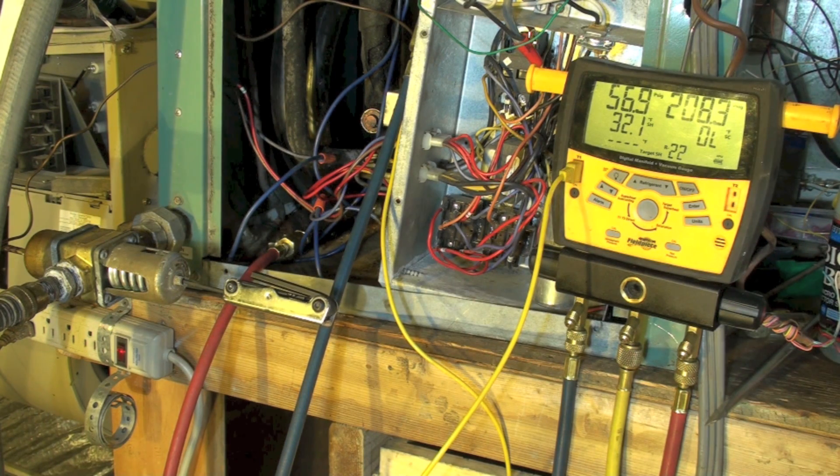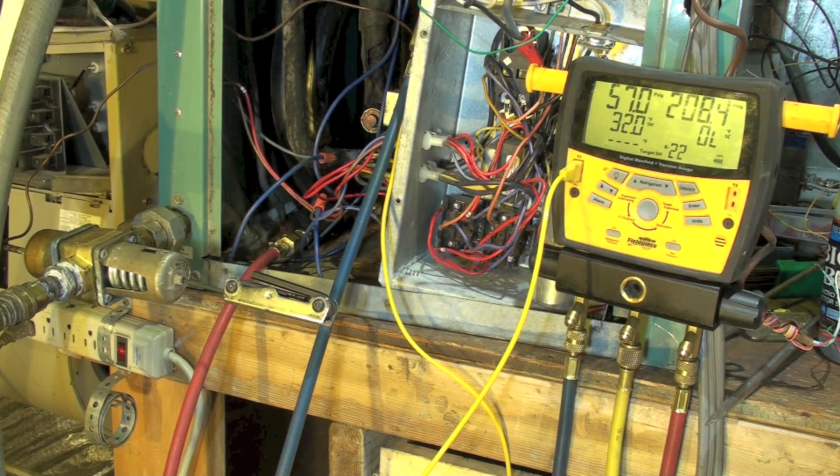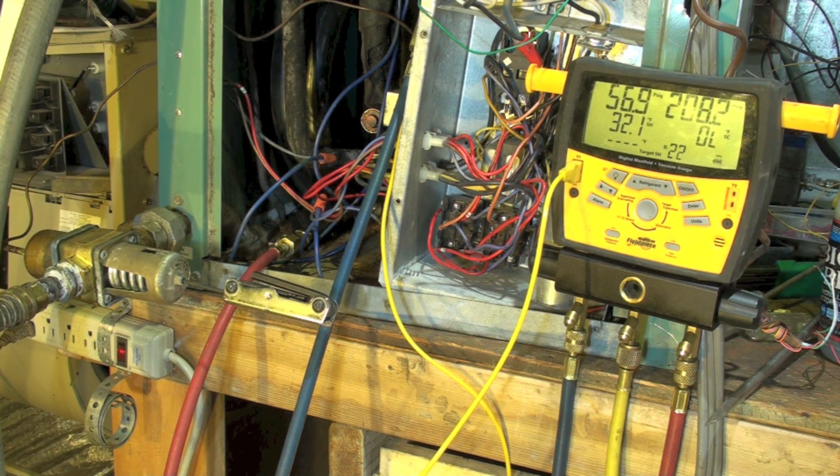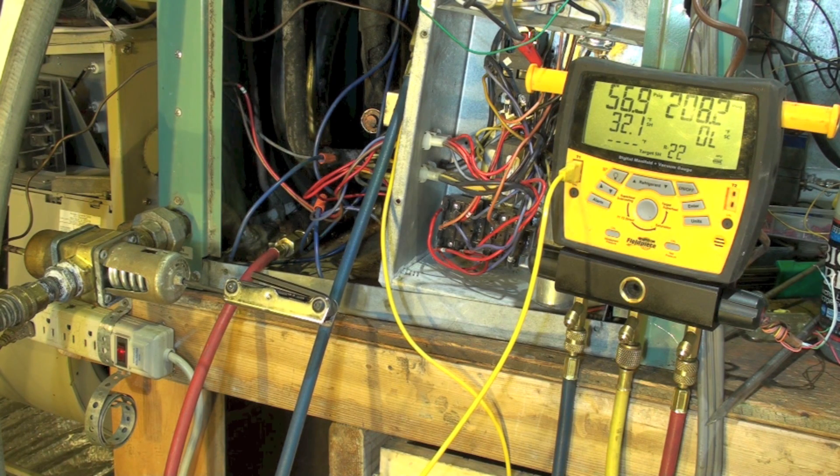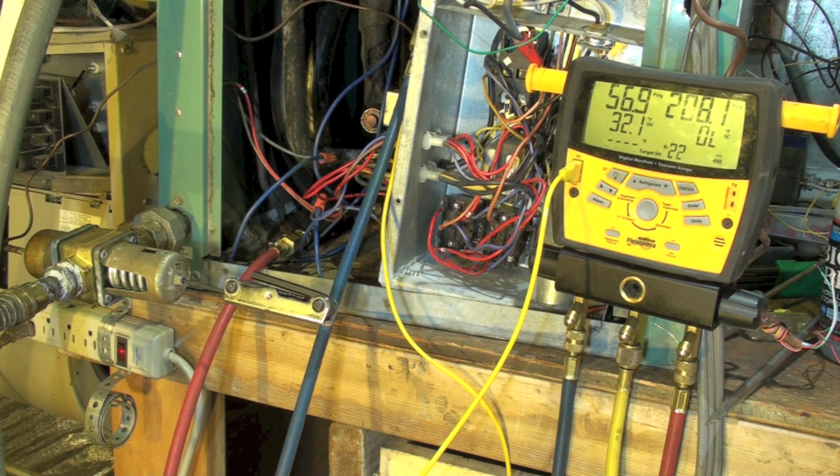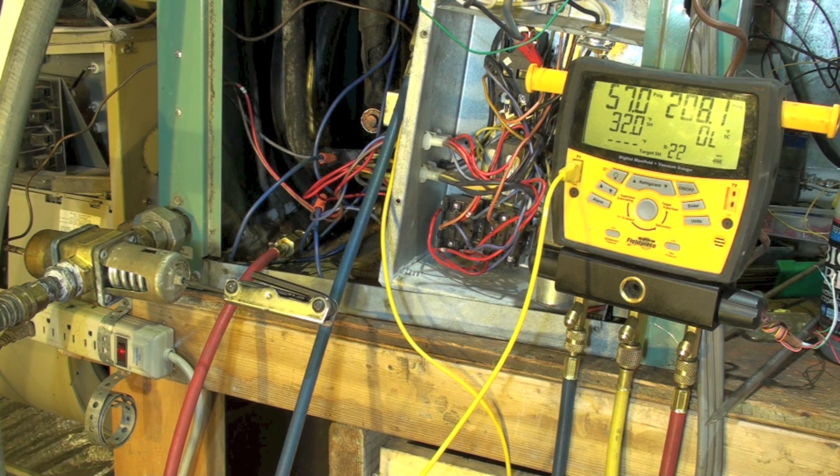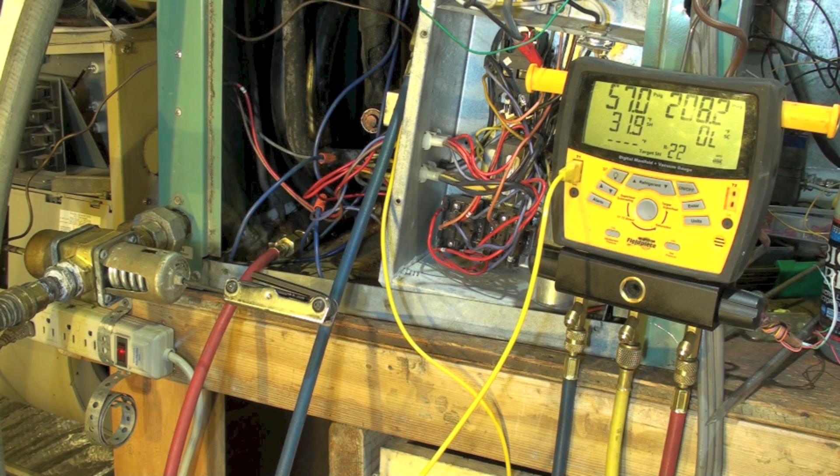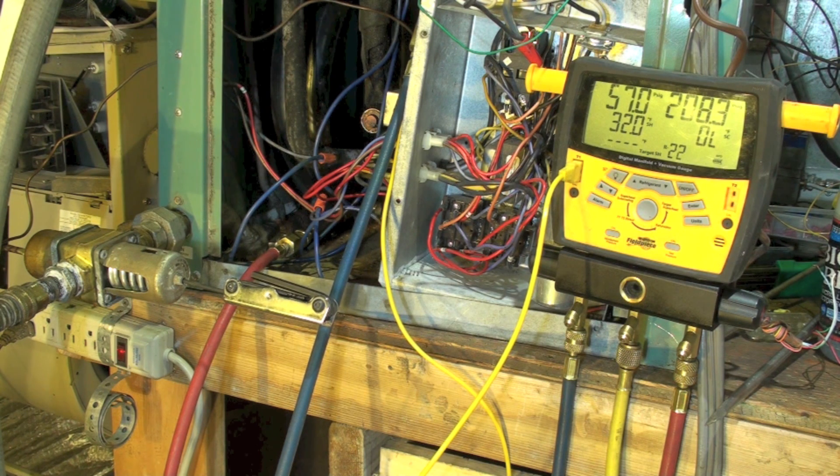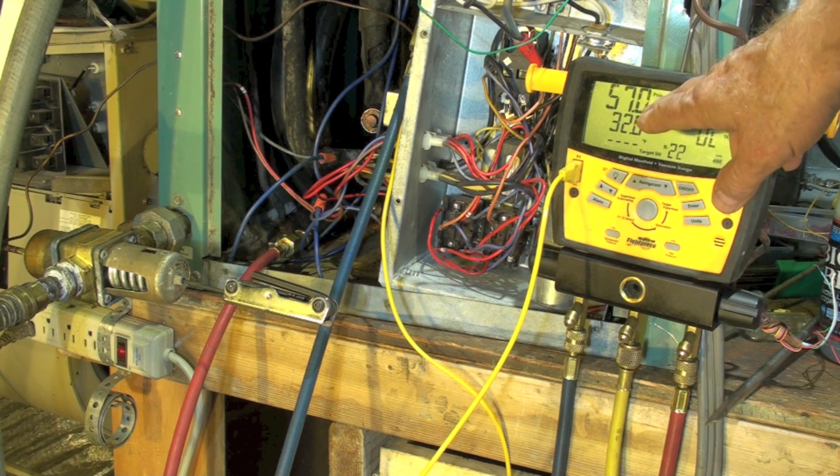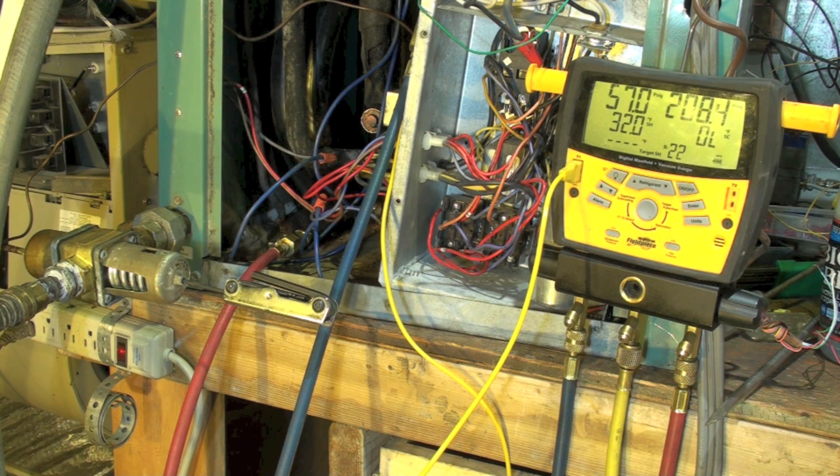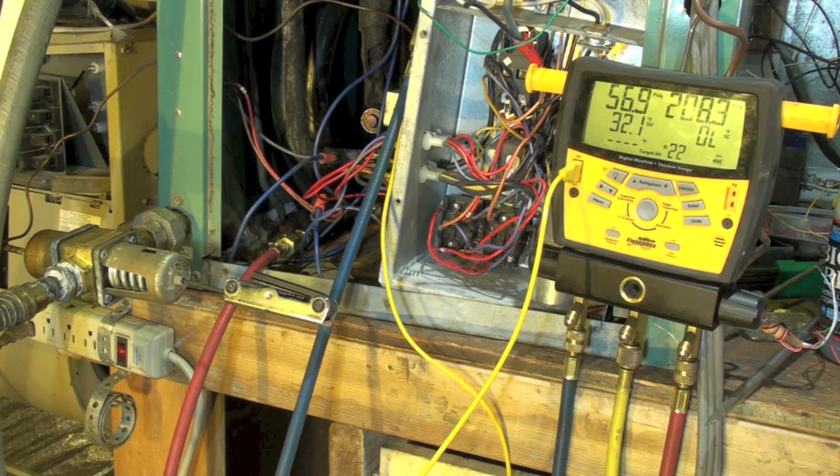Okay, one more time. Now my discharge water is 87 degrees now. So you're kind of tied in on these machines to a certain way of charging it. I don't think these older machines like this were all that energy efficient - one thing I think the indoor coil was a little too small. But I just kind of wanted to show you this. Now I'm gonna jack this back up again. Remember running about 87 degrees discharge water temperature, and we're down here where our suction pressure is below what I'd want to have it.